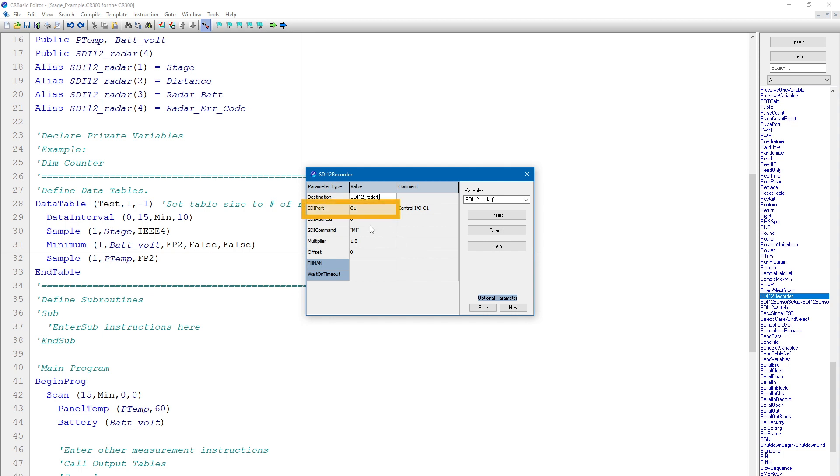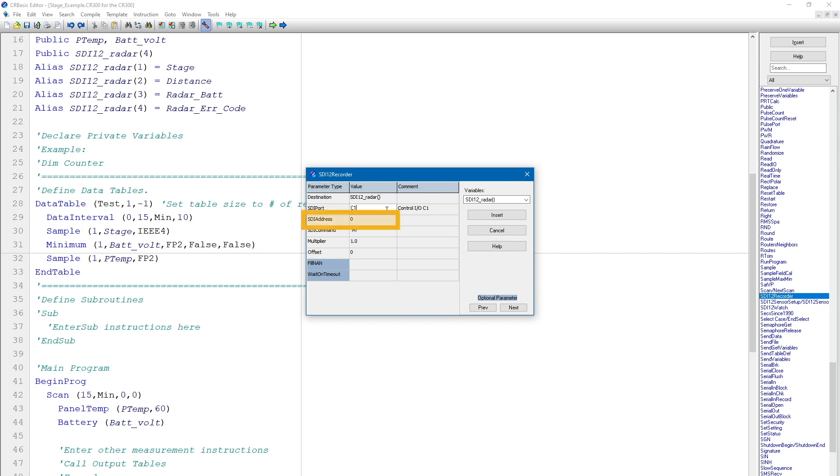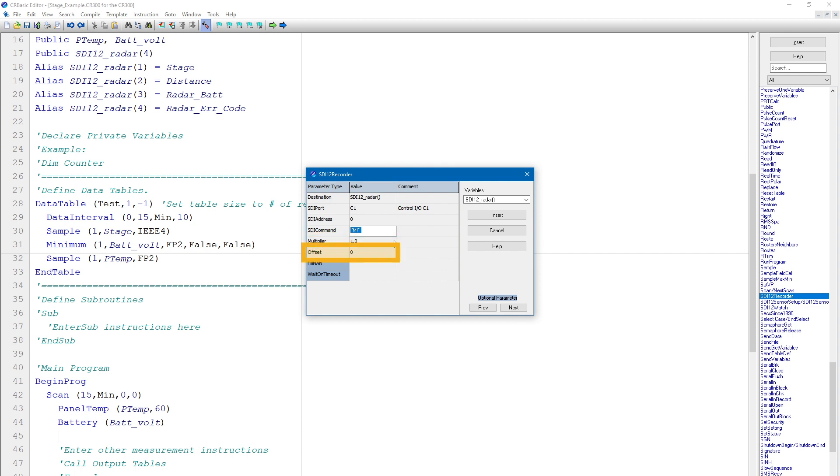Next, I right-click in the SDI port parameter box to see a list of available data logger terminals. In this case, the SDI 12 data line for the sensor is physically wired to terminal C1. So I select C1 for the SDI port. The default SDI 12 address is 0, so I will leave that alone. The default SDI command is M! which is also fine. I will also leave the multiplier and offset at their default values.